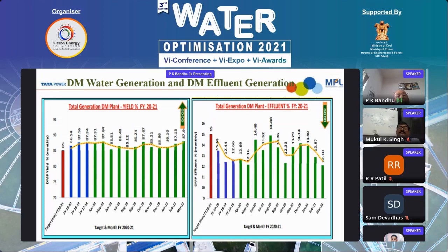So for the DM plant generation, this graph is showing the reduction of the effluent generation, and how this has been possible. This has been possible because of regular maintenance practice, and second, the timely renewal of the resins and reducing the backwashing quantity. The DM generation has also been reduced because the boiler water chemistry was maintained so stringently, so the process blowdown water required is very little. So the DM water generation also reduced, and the DM plant effluent generation also reduced.